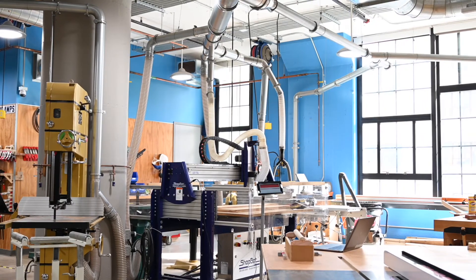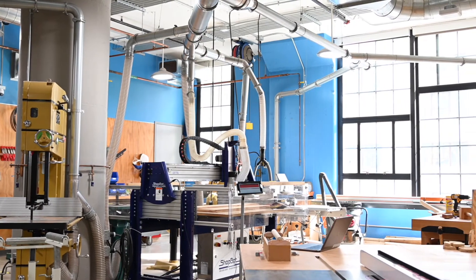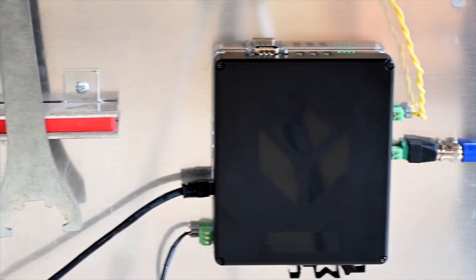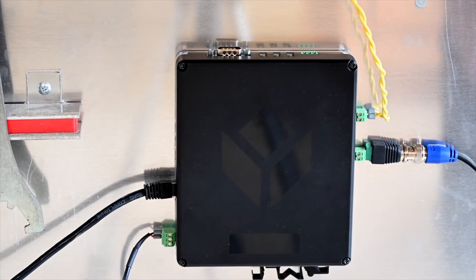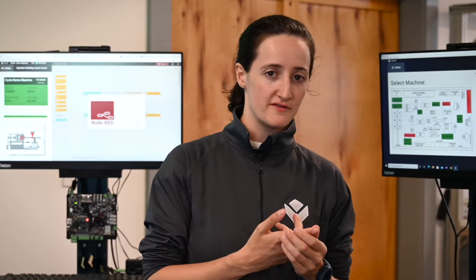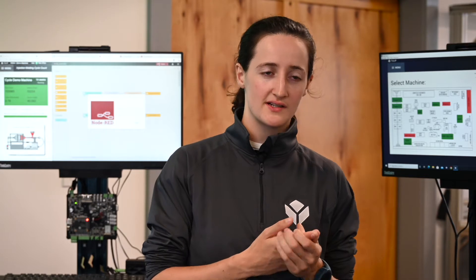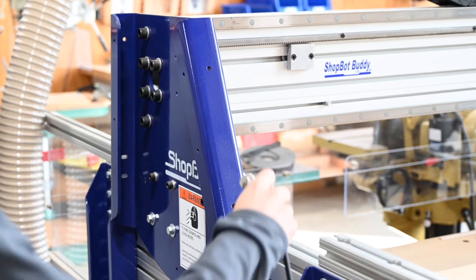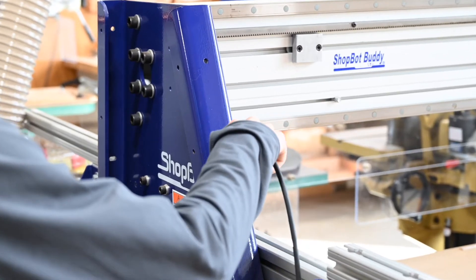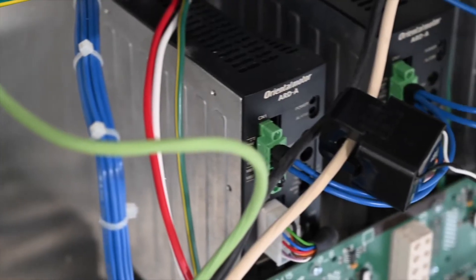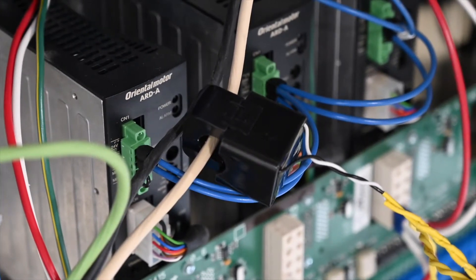At Autodesk we were testing using the Edge.io to monitor a CNC mill, and to do this we were using both a vibration sensor and a current clamp. The vibration sensor was placed on the chassis of the CNC mill, and the current clamp was hooked up to the power supply.